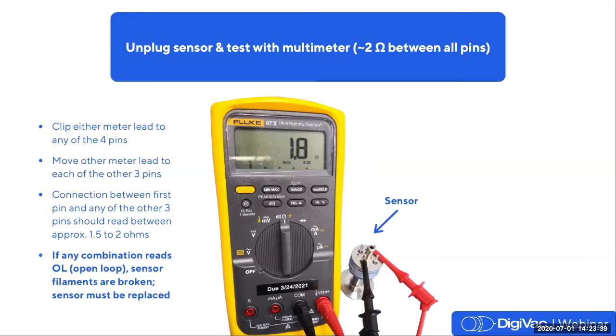We clip either meter lead to any pin and move the other lead to each of the other 3 pins. The connection between that first pin and any of the other 3 should read between about 1.5 to 2 ohms. If any of those combinations read OL, or open loop, the filaments inside are broken and the sensor needs to be replaced. Unfortunately, the filaments inside can't be repaired, and if they come broken apart, that is essentially, for lack of a better term, curtains for the sensor. So it would need to be replaced at that point.